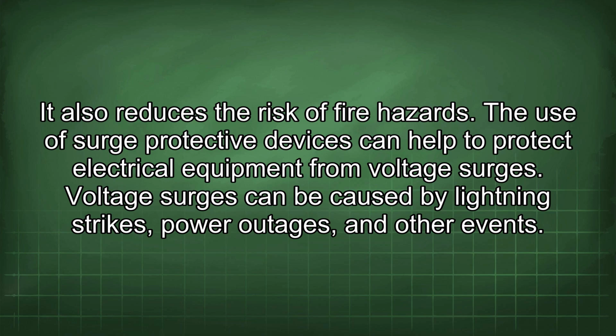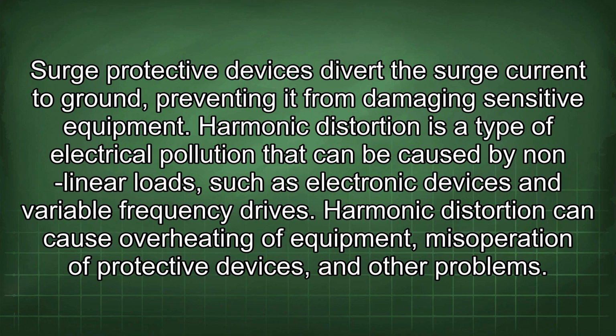The use of surge protective devices can help to protect electrical equipment from voltage surges. Voltage surges can be caused by lightning strikes, power outages, and other events. Surge protective devices divert the surge current to ground, preventing it from damaging sensitive equipment.